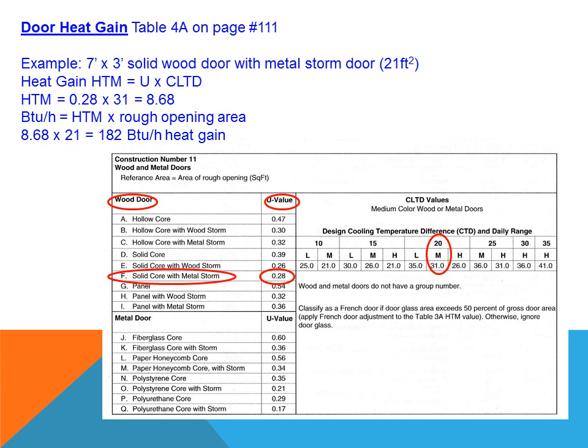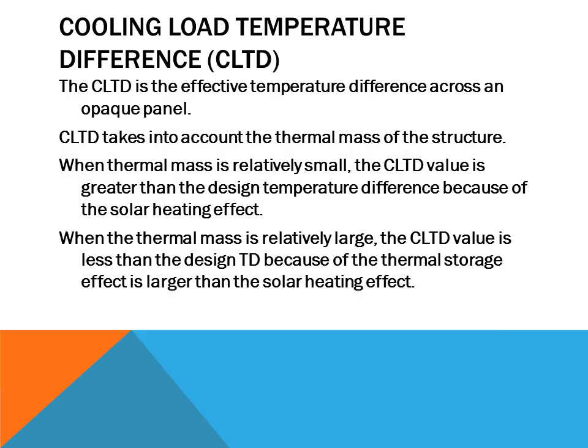As we've explained before, the Cooling Load Temperature Difference — CLTD — is the temperature difference in the summertime between the indoor temperature and the outdoor design temperature. We need to look at the table to determine that number based on where the structure is located. In this project, we're using Waukegan as the factor for both summer and winter heat load design outdoor temperatures.